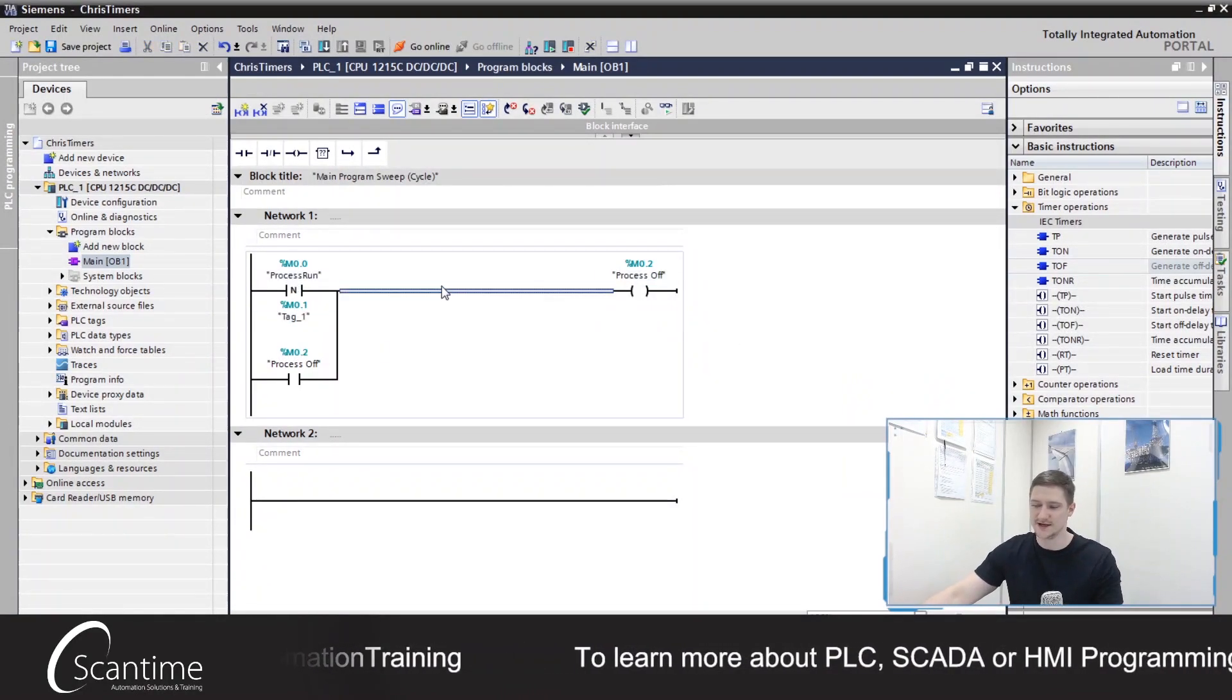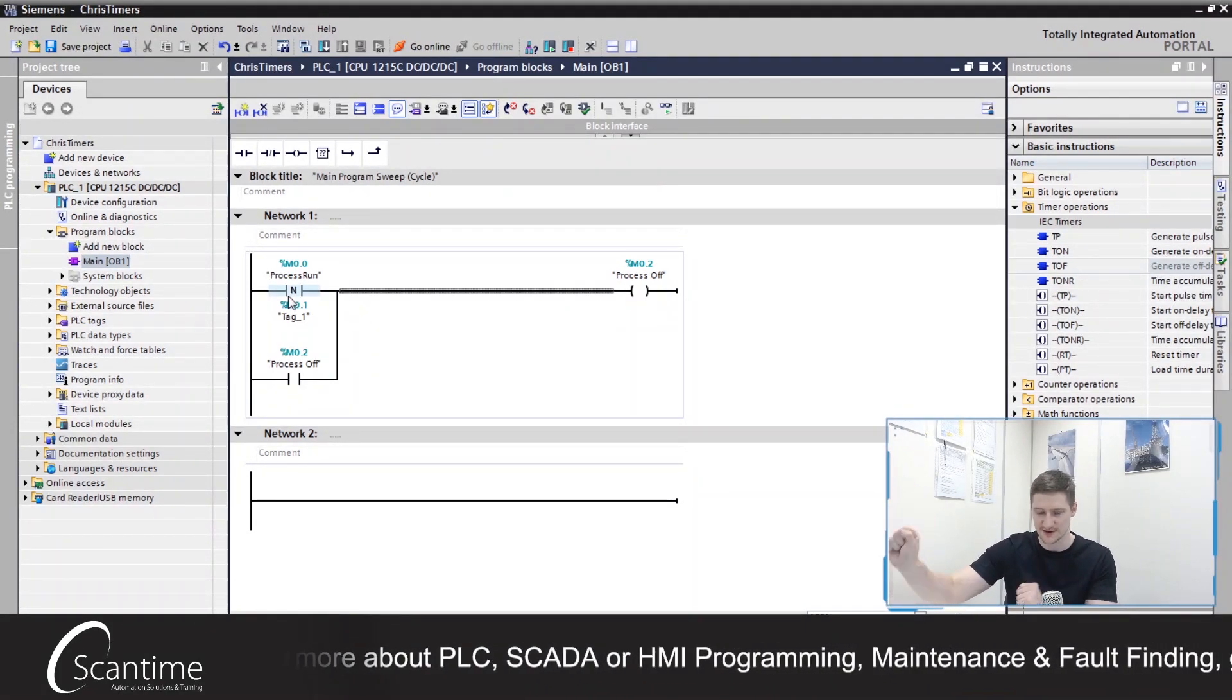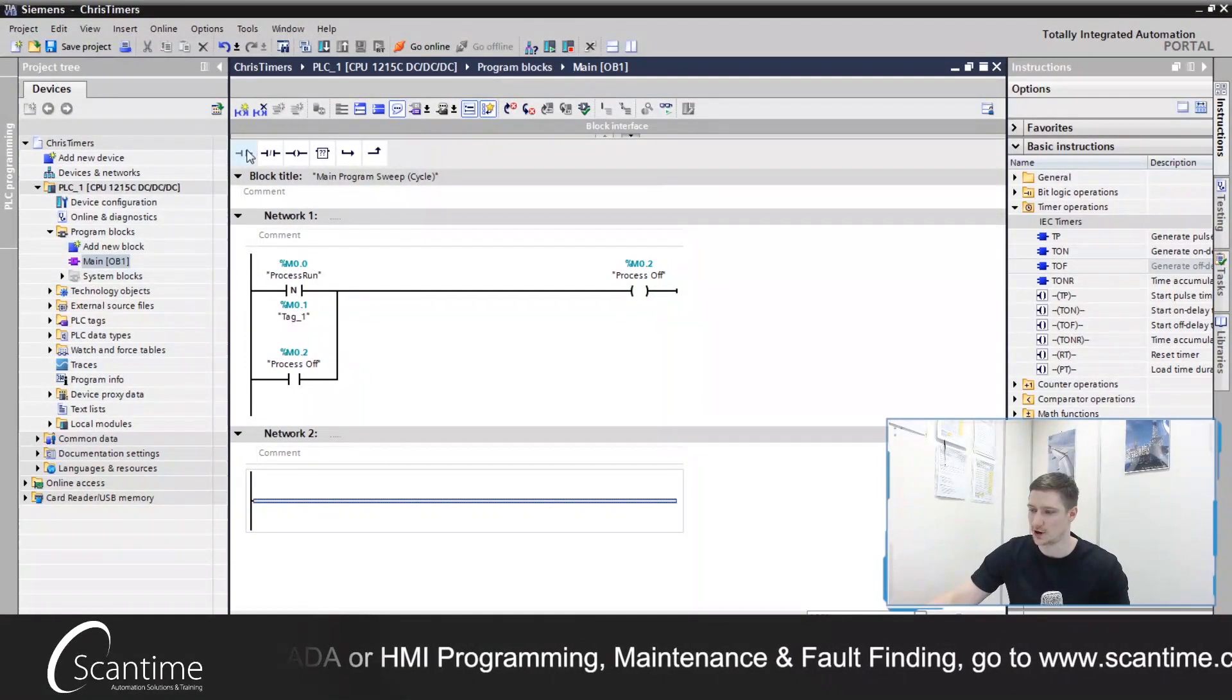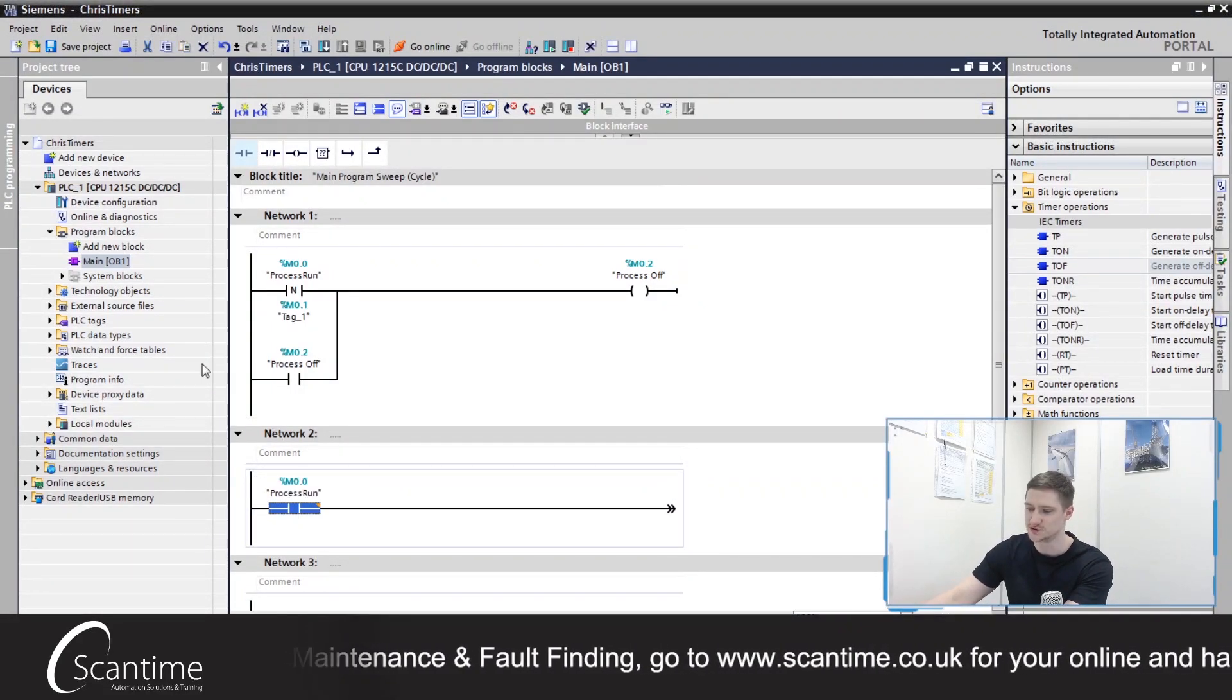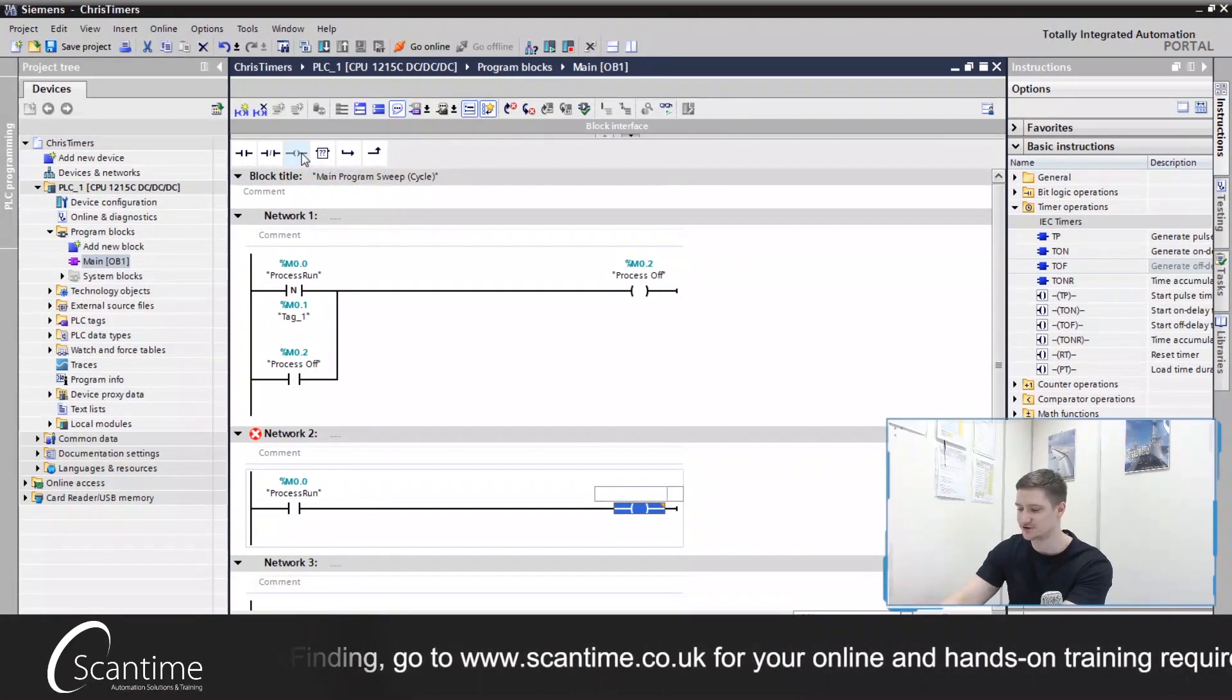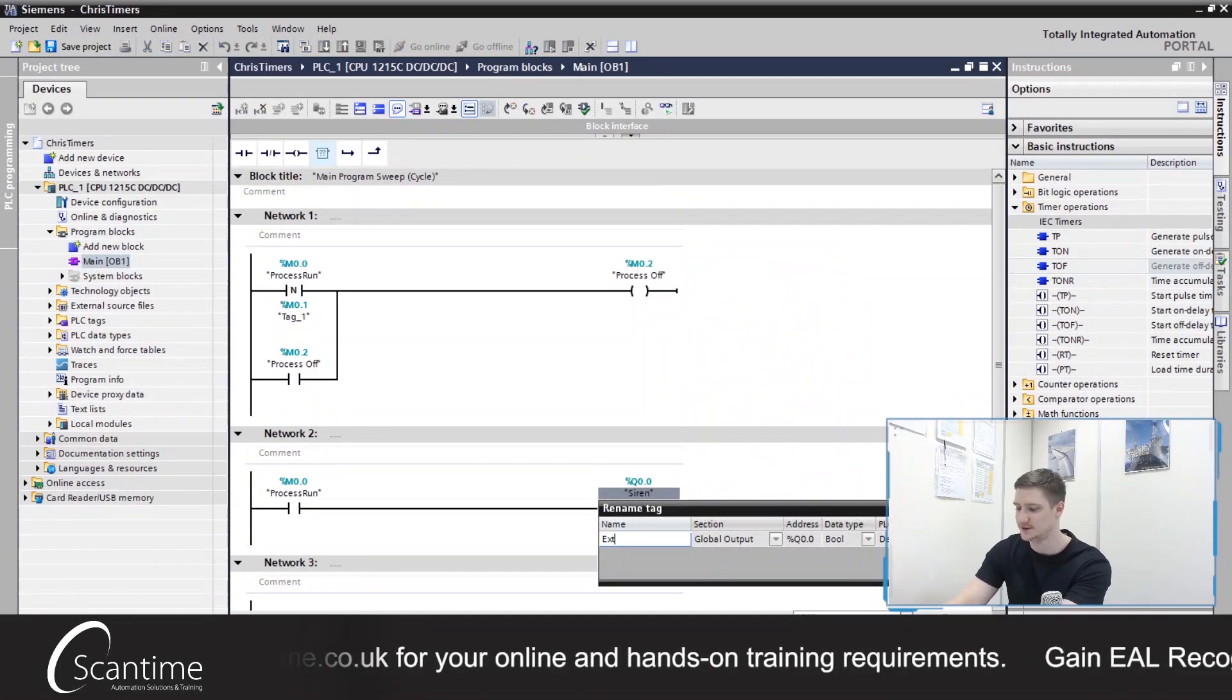We need to reset this latch, but I'll come up to that later on. So when the process run turns off, our process is off and that will then latch on. Now what we do is on our next network, we need to again control this via our process run signal. So when the process is running, we want to turn on our extraction fan, Q0.0.